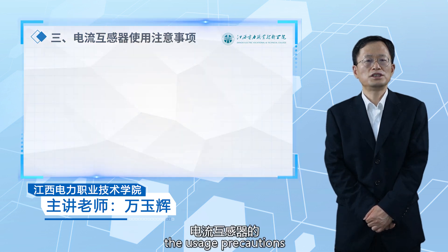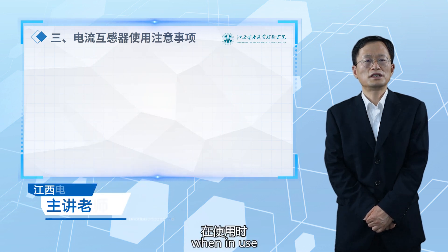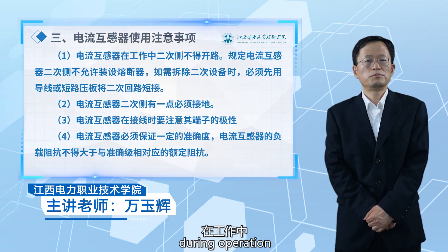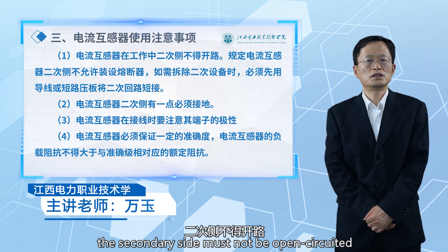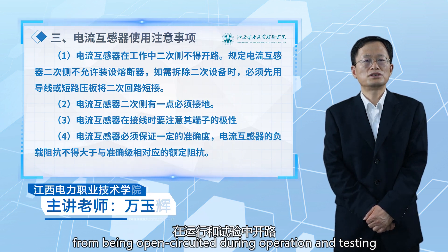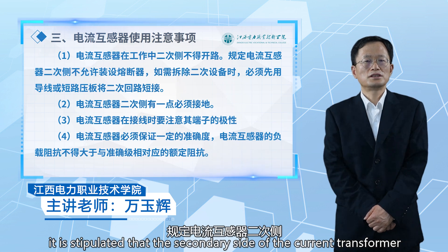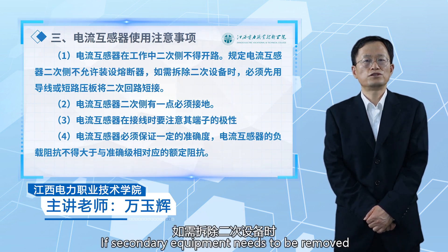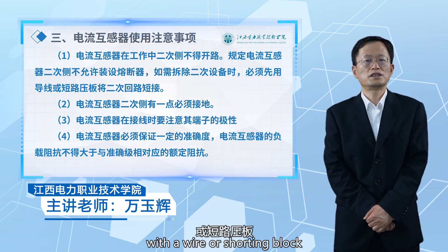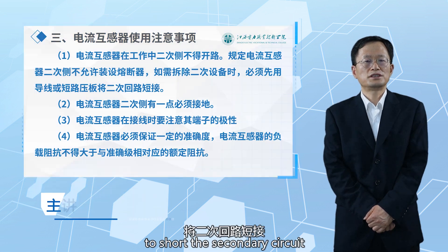Finally, we will introduce the usage precautions of current transformers. When using current transformers, the following points must be noted. During operation, the secondary side must not be open-circuited. To prevent the secondary side from being open-circuited during operation and testing, if secondary equipment needs to be removed. If full removal is necessary, it must first be short-circuited with a wire or shorting block to close the secondary circuit.